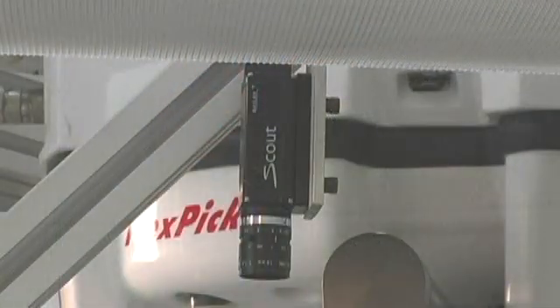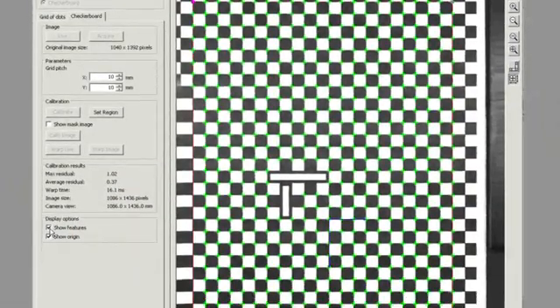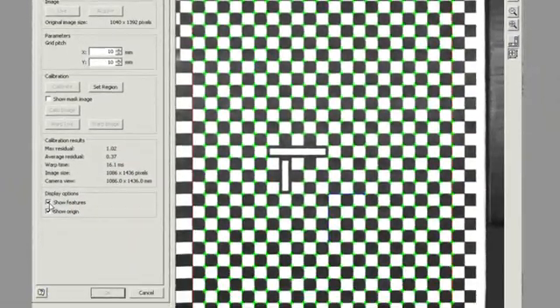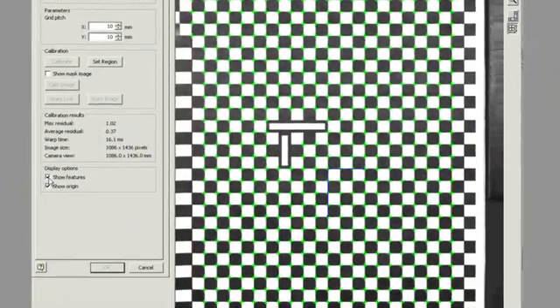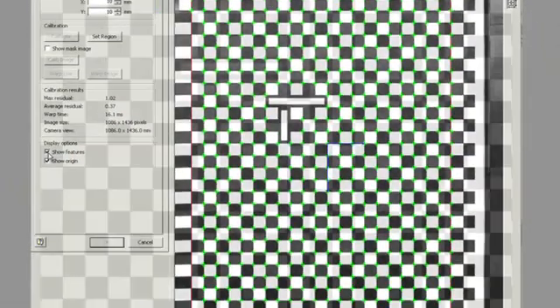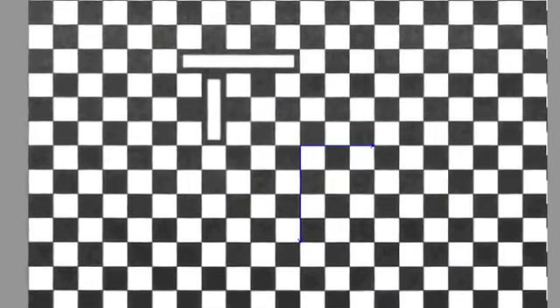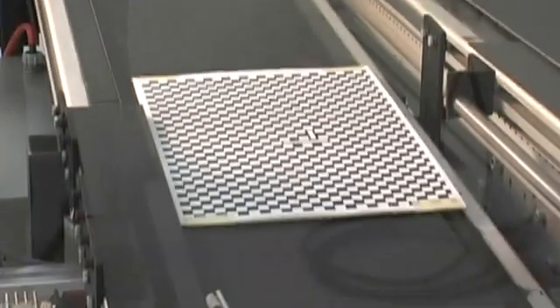Now that we've created a line, the next step is to calibrate the camera to the first conveyor. The camera is calibrated using a grid that has special features for determining the origin of the X and Y axes. The size of the blocks let us know the actual size of the parts, as well as their location on the conveyor.